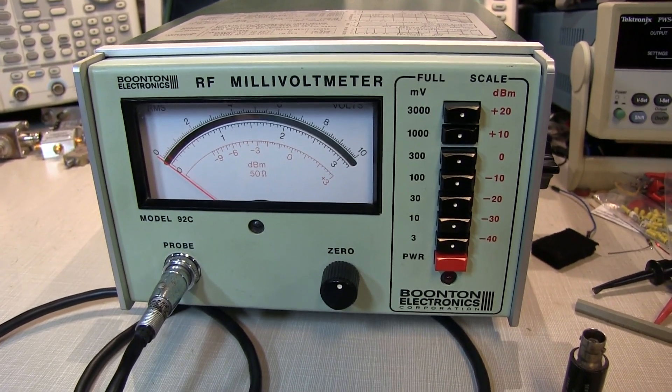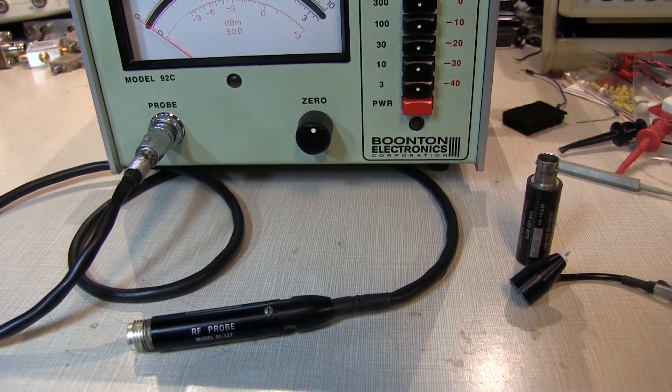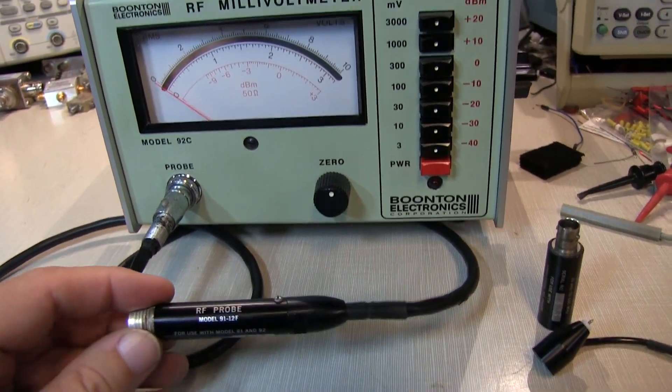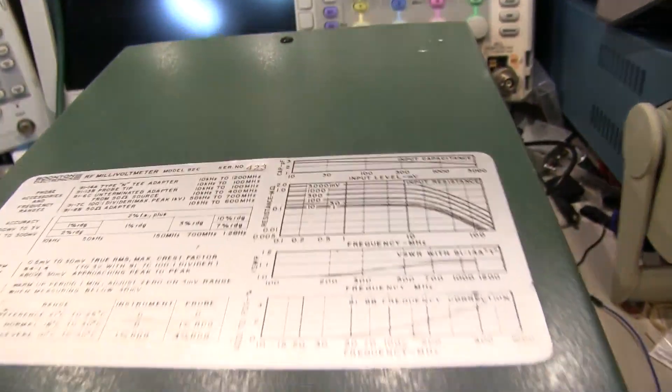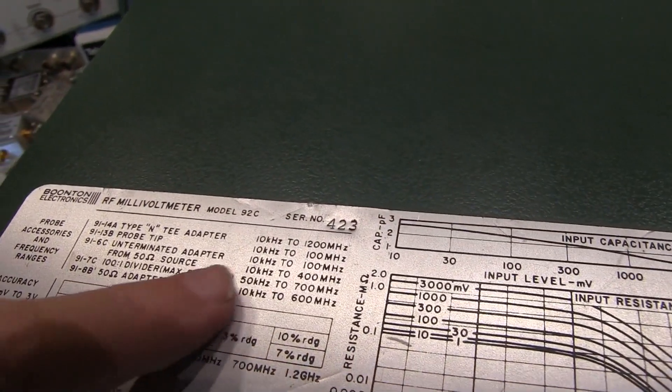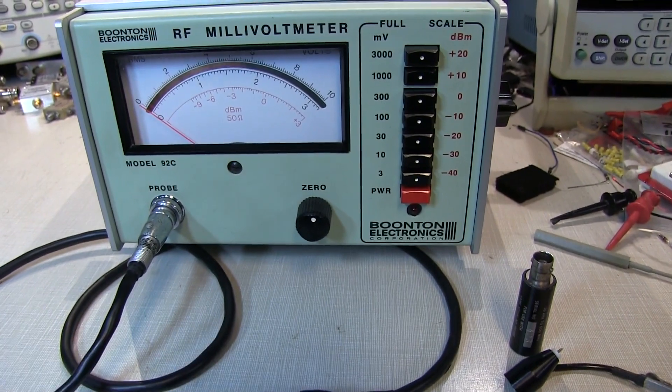Now if you're going to look for one of these meters, you really want to look for one that comes with the original probes, and the reason for that is that the probe and the meter were calibrated together. If we look at this probe, you might be able to see that it says this probe was calibrated for serial number unit 423, and if we look at the top label of the meter itself, serial number 423. So this is the original probe that came with this meter, and that's a really nice find.